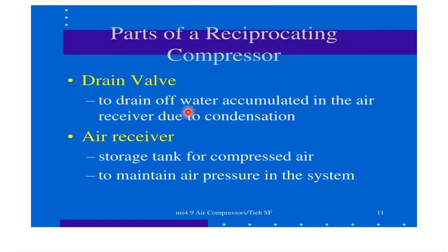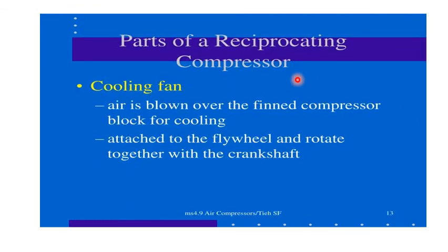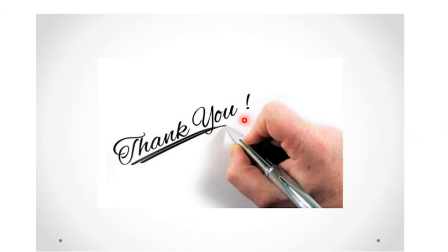The drain valve drains off water accumulated in the air receiver due to condensation. The air receiver is the storage tank for compressed air to maintain air pressure. The compressor block contains the working parts of the compressor including the inlet valve, outlet valve, and piston, as well as the crankshaft and connecting rods. The cooling fan blows air over the compressor block for cooling and is attached to the flywheel, rotating together with the crankshaft.